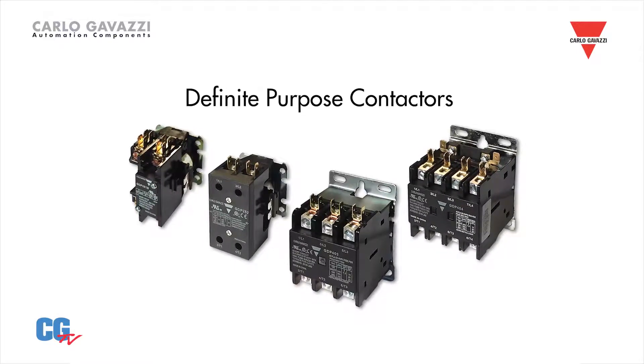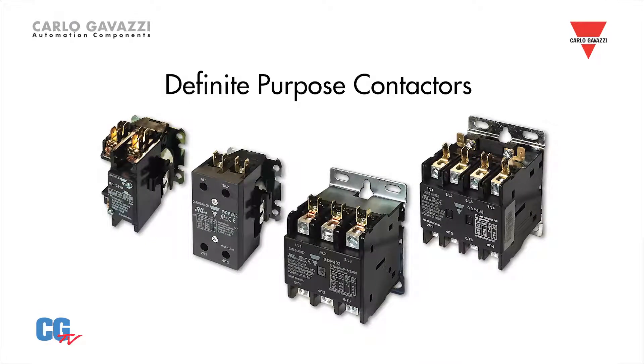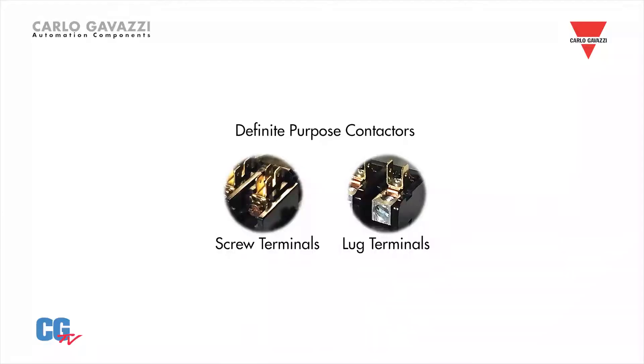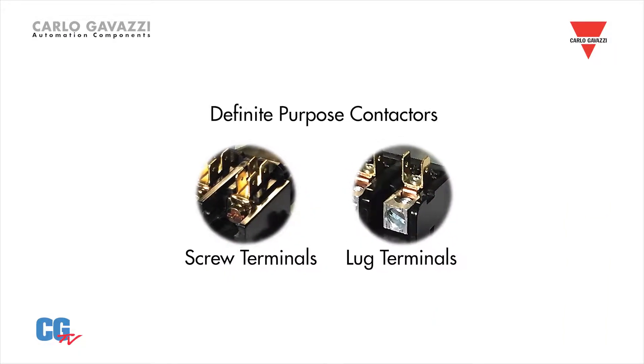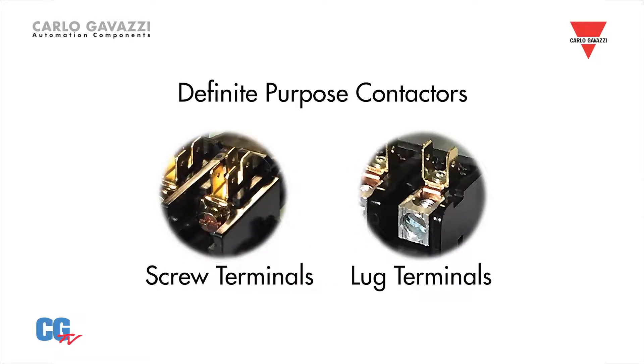The DP series is available in one pole with shunt, two pole, three pole, and four pole options. They are capable of switching resistive loads up to 100 amps and inductive loads up to 90 amps. Horsepower ratings are also available on most models. A choice of screw or box lug power terminals are available on most contactors, with fast-on connections provided on all coil and power terminals.